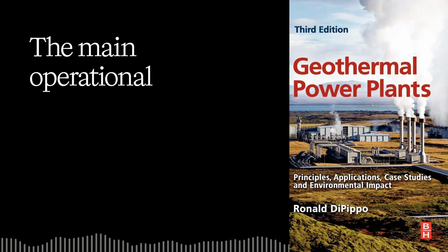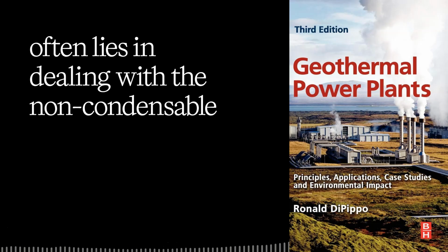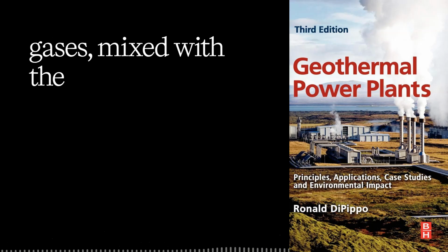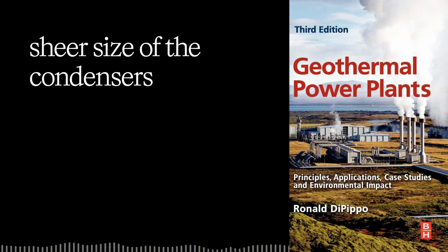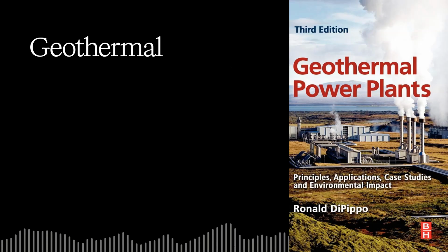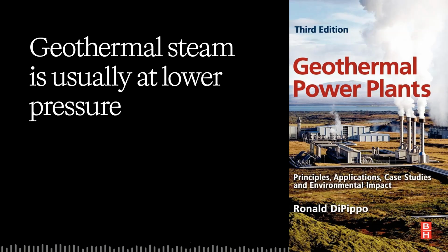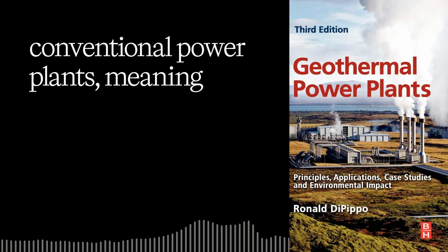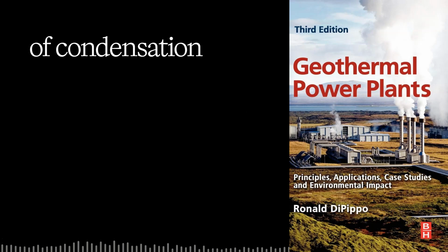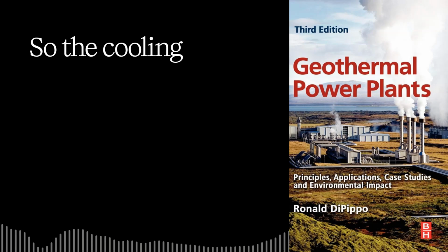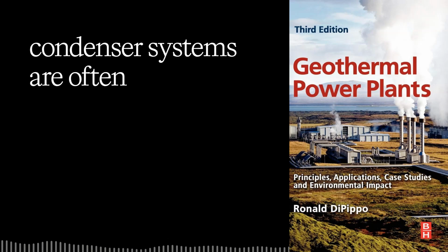The main operational complexity often lies in dealing with the non-condensable gases mixed with the steam and the sheer size of the condensers needed. Geothermal steam is usually at lower pressure than in conventional power plants, meaning it has a very high heat of condensation that needs to be removed. So the cooling towers and condenser systems are often huge.